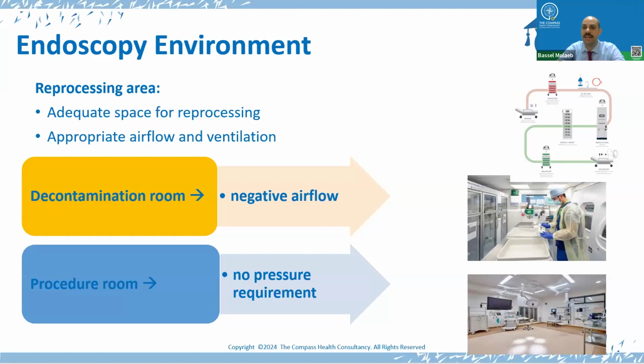Reprocessing areas should be accessible only to authorized personnel. The workflow should be unidirectional. We mean by that movement from the dirty to the clean area, in order to minimize the opportunity for cross-contamination. The dirty and clean areas should be physically separated from one another. When reprocessing occurs in two rooms, the decontamination room should have negative airflow, and the temperature, in addition to the humidity levels, should be in compliance with the local and facility requirements.